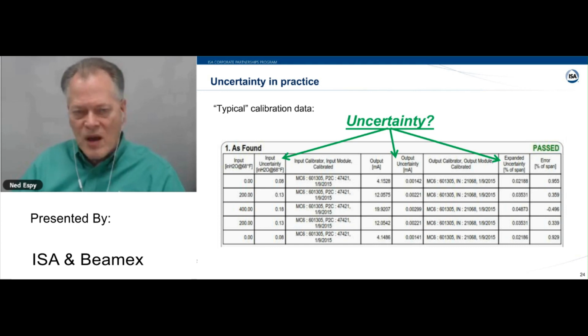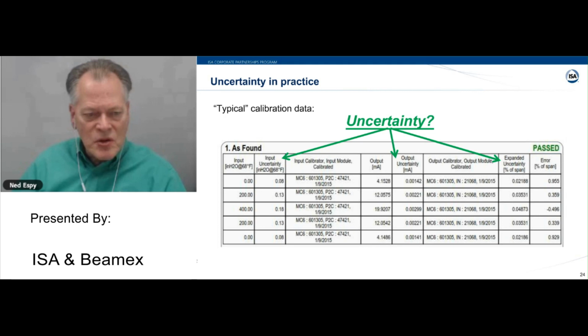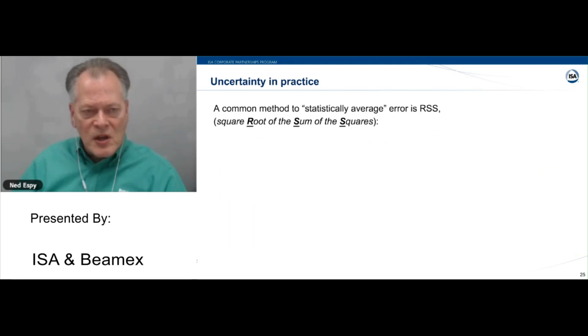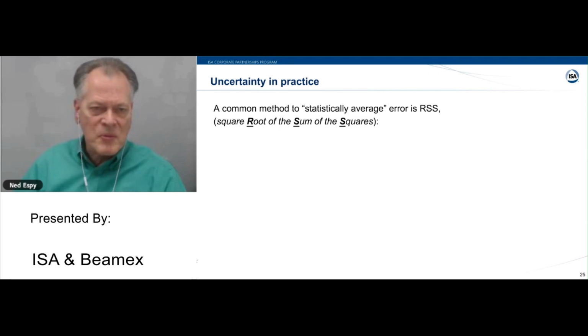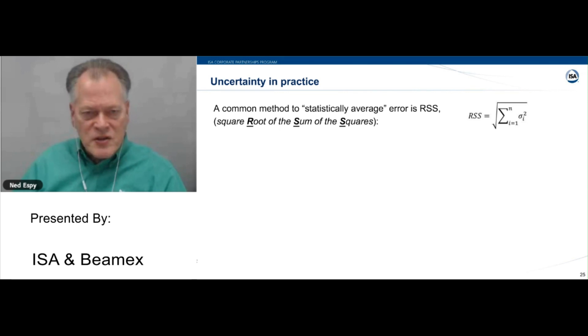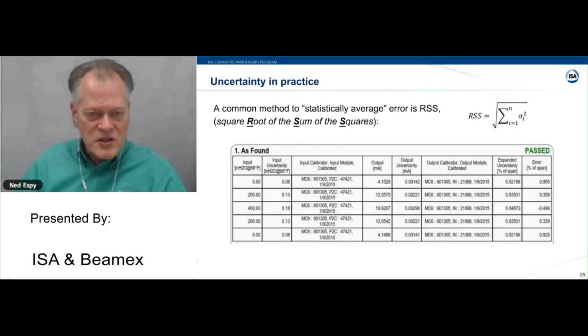But then over on the far right, where it says expanded uncertainty, how do you combine the input and the output? Well, you want to convert everything to a percent of span. So how do we do that? Let's show you the math a little bit. Since we're talking about type B errors, a good statistical method is a way to average things. A lot of people call it RSS, the square root of the sum of the squares. And here's a crazy formula, and actually Rich is going to use this as well.